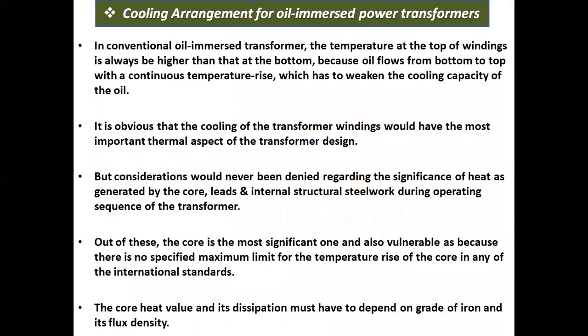Cooling arrangement for oil-immersed power transformers. In a conventional oil-immersed power transformer, the temperature at the top of the windings is always higher than that at the bottom because oil flows from bottom to top with a continuous temperature rise, which weakens the cooling capacity of the oil. It is obvious that the cooling of the transformer windings is the most important thermal aspect of the transformer design.